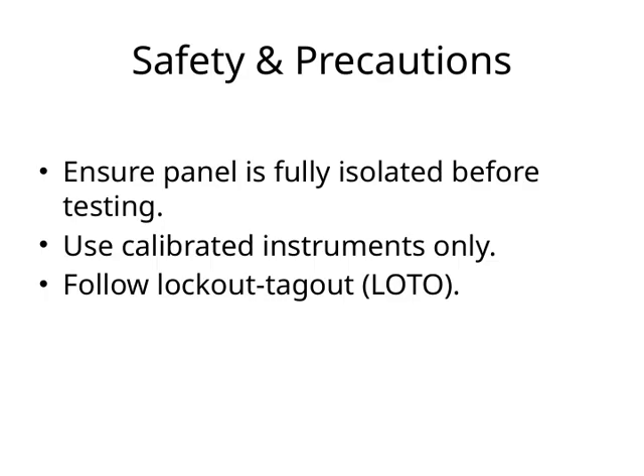Let's talk about safety and precautions, which are absolutely essential when working with electrical panels. First, always ensure that the panel is fully isolated before you start testing. This means disconnecting it from the power source to prevent any accidental energization. Next, only use calibrated instruments. Using properly calibrated tools ensures that your measurements are accurate and reliable, reducing the risk of errors.